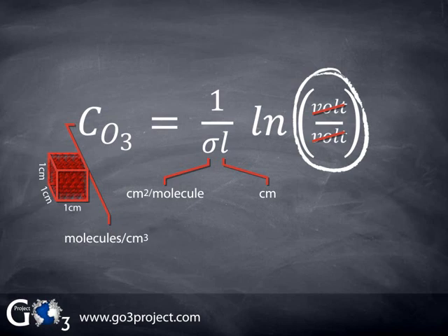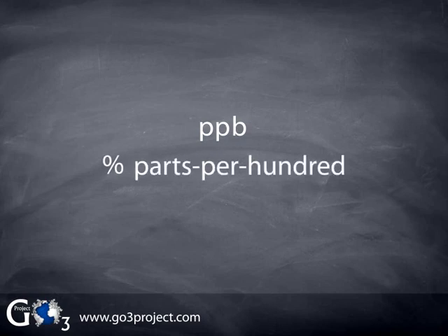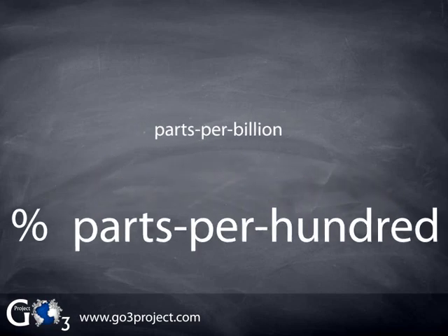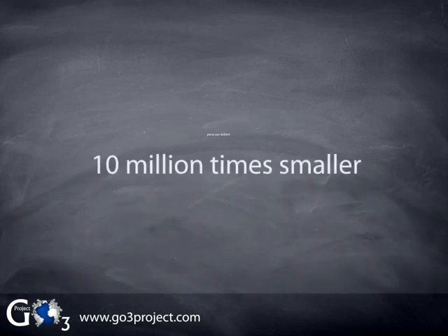As we have seen, ozone monitors fundamentally measure ozone concentrations using units like molecules per centimeter cubed. What is measured is the number of molecules in a cubic centimeter of air. Atmospheric scientists prefer to express ozone levels in fractional units such as parts per billion or PPB. We are all familiar with the fractional unit of percent. Like percent, the unit parts per billion is a fraction. Percent is parts per hundred. Parts per billion or PPB are ten million times smaller than percent.